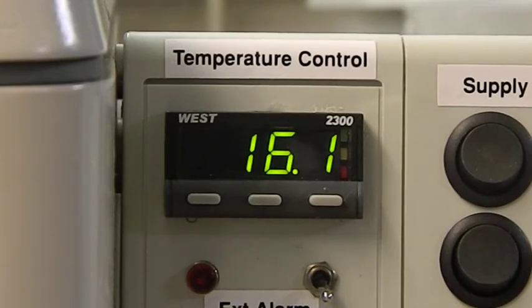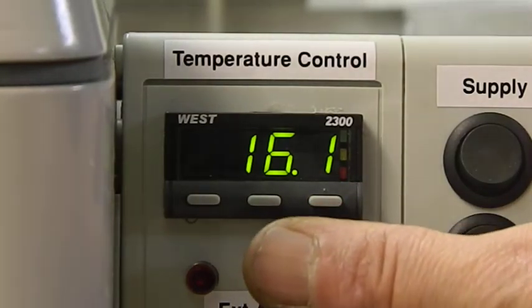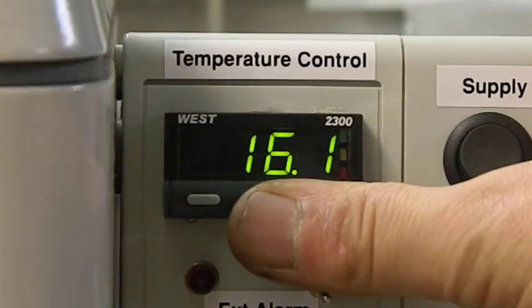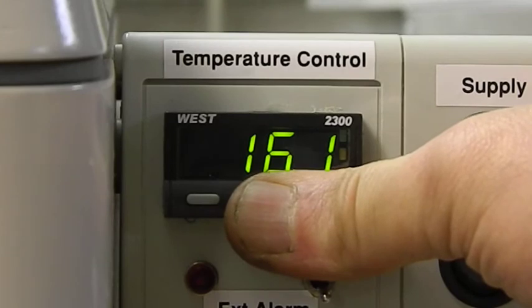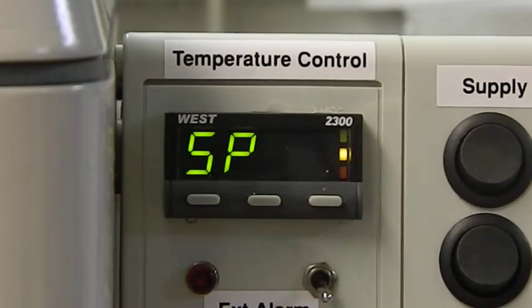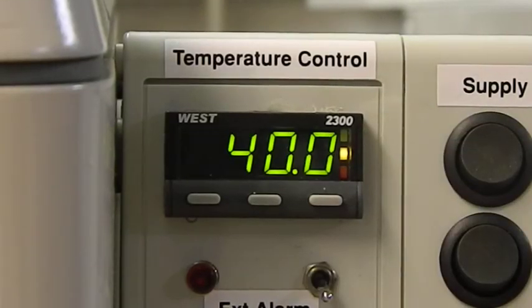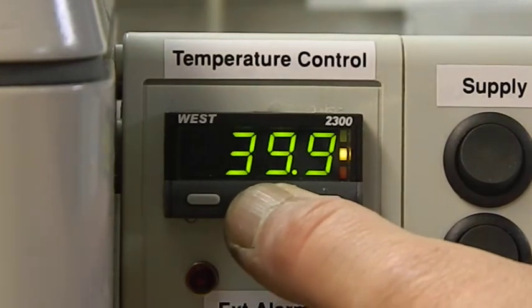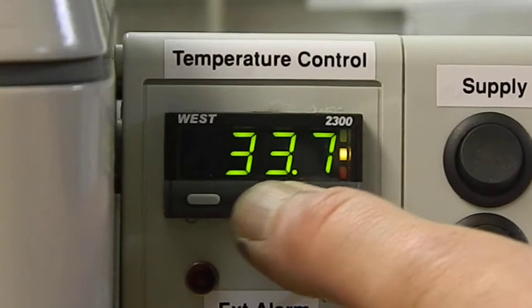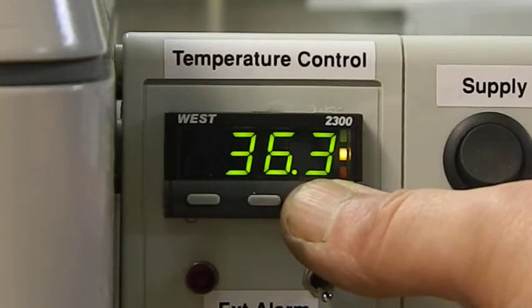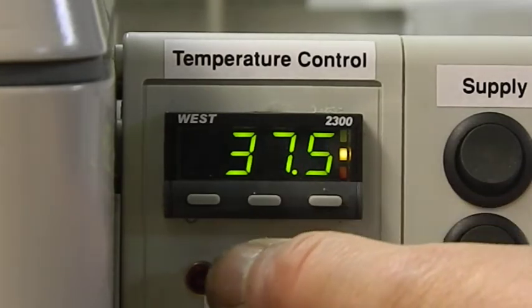Now we'll go in and put some of the finer controls in. So to get into this parameter, you press the right and center buttons together and hold them. There we go, SP. SP is the set point. This one's set to 40 as a default, so we'll take that down to 37. We want the 37.5. There we go.